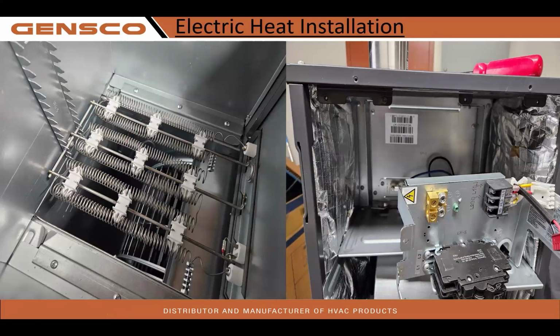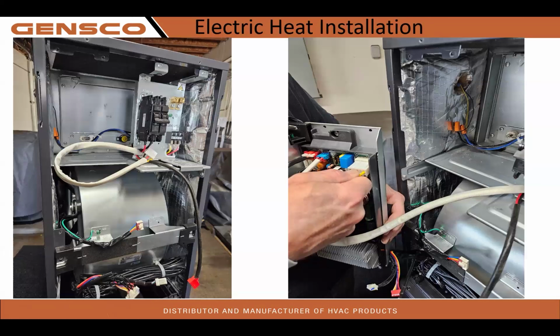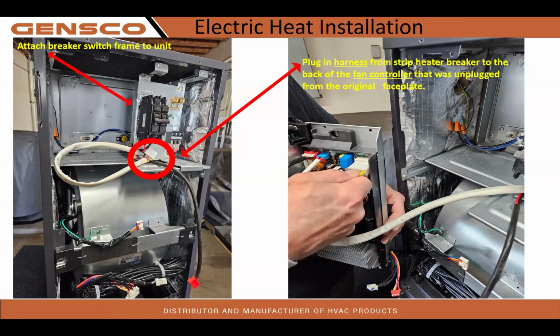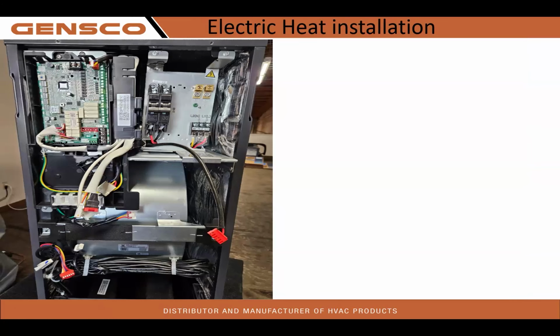There is a look at the heat kit installed, and these are our back wall mounting brackets. Make sure it's true plumb and level. We are merely going to plug in the heat kit right there. We are going to set our breaker. 2 screws. This just snaps onto the bottom. Plug in the harness from the strip heat breaker, back of the fan control. And there is a look at our heat kit installed. Everything is nice. There's our breaker. There's our line 1, line 2, and ground. Some ground lugs right there.